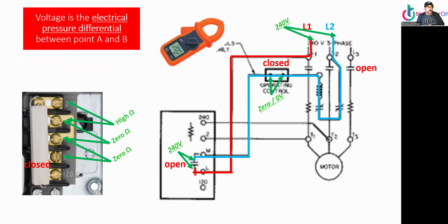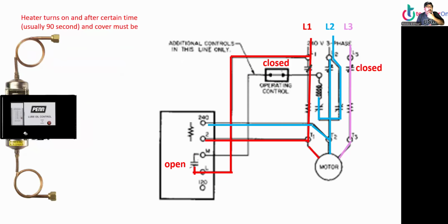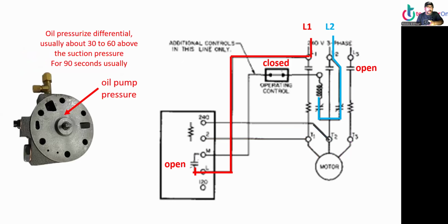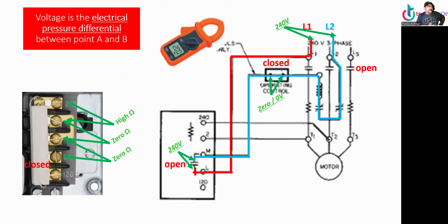So what happens is, when it opens, no more power. It will cut off power to the contactor. Now to check it: voltage is the electrical pressure differential between point A and B. So if it's open, we should have 240 volts between the M and L because it's open. We're reading the blue and the red line. Now, on top, L1 and L2, we should read 240 volts.